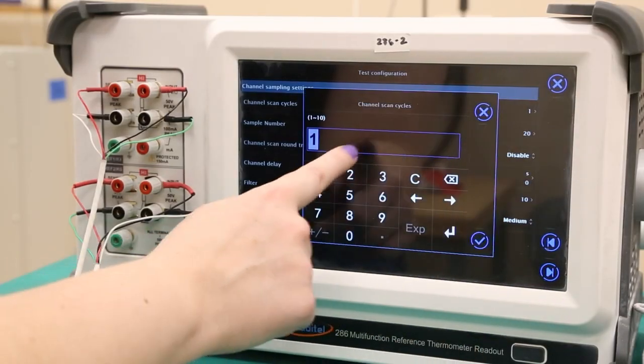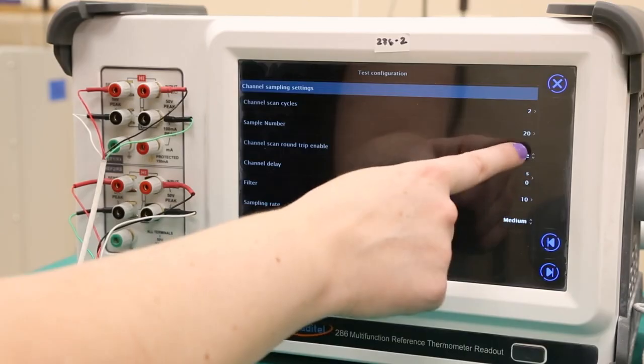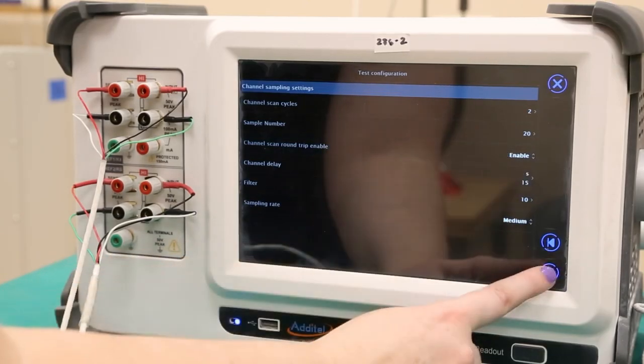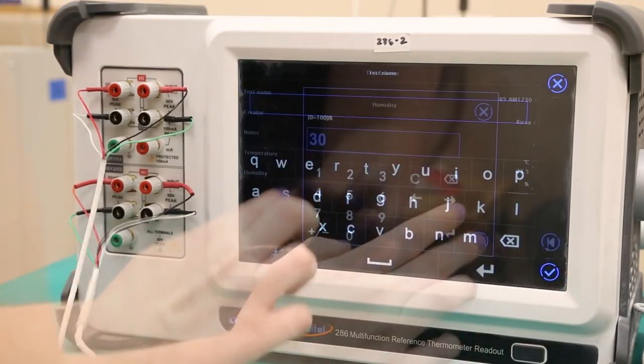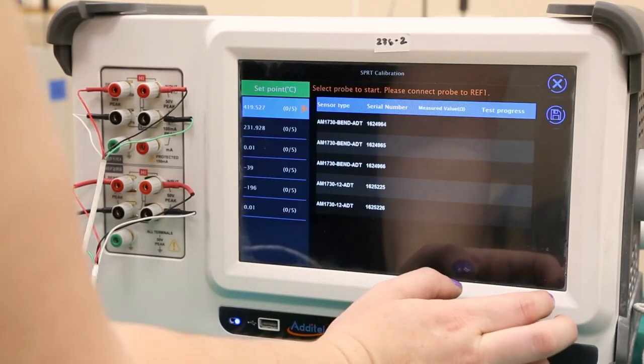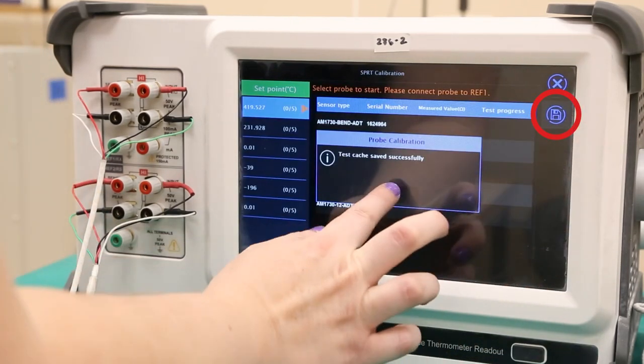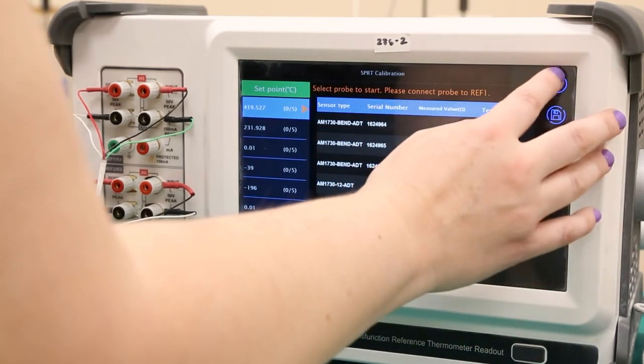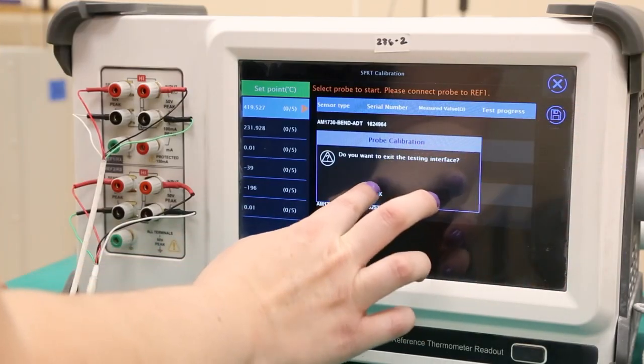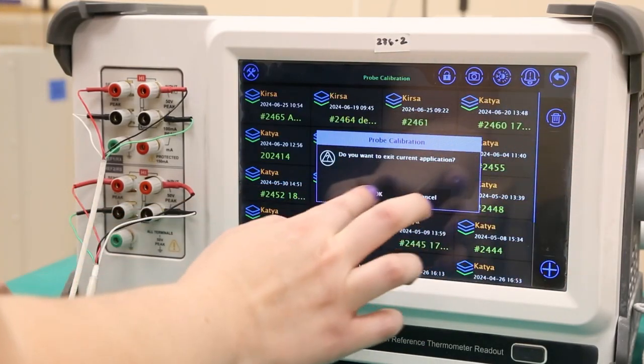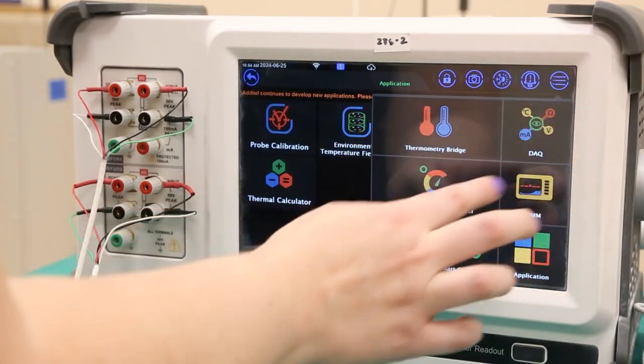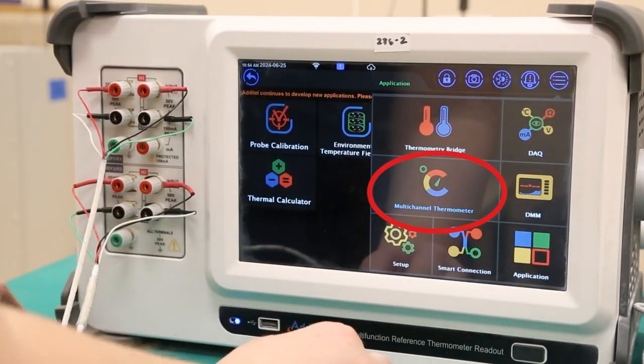On this screen, sampling and scan settings can be changed for the entire test. Finally, the test can be named and saved with relevant metadata. Press the checkmark button, then the Save button to save this newly configured test. From here we are ready to start, but first want to check that the zinc fixed point cell has reached the freezing point. For this we will select the multi-channel thermometer from the application menu.